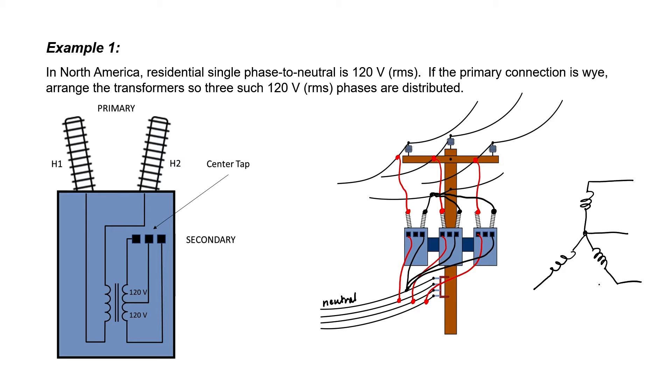If we were to do that, then we would have 240 volts RMS from all of the three phases to neutral. What we should instead do is connect the center tap to neutral. We'll let that third connection float because we don't need it.